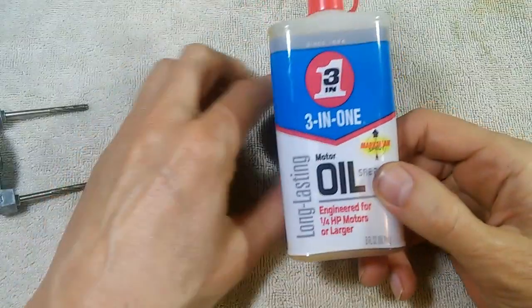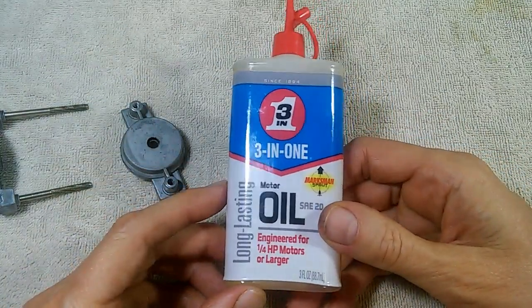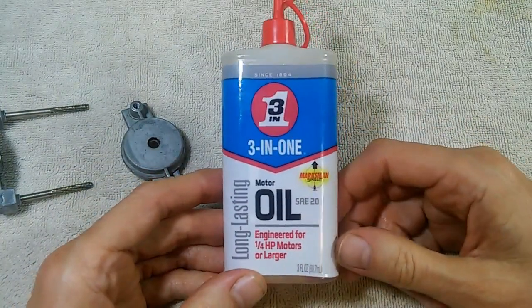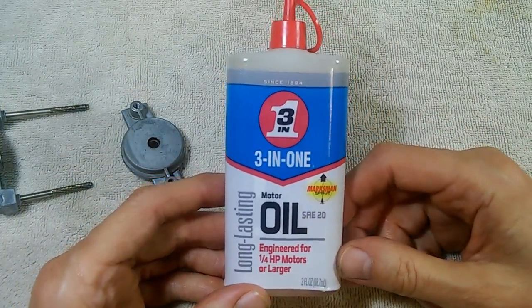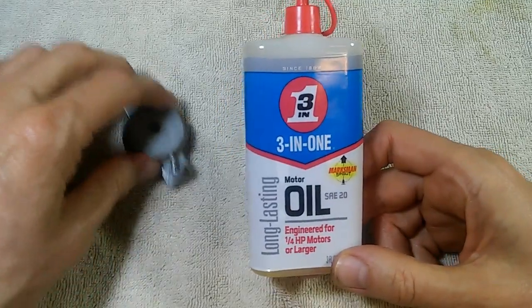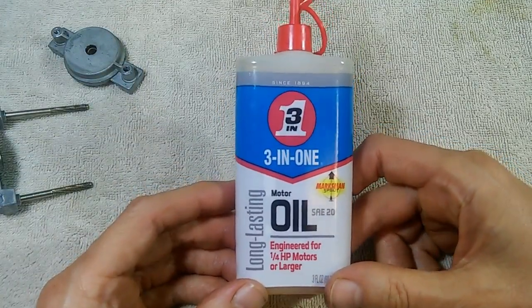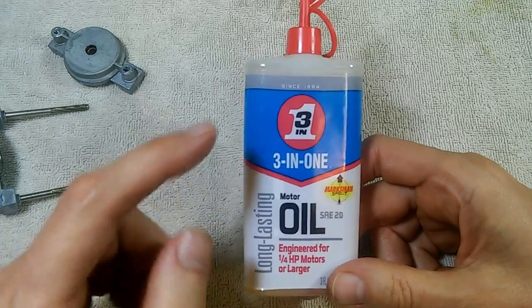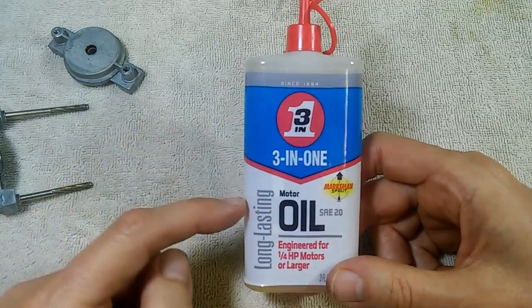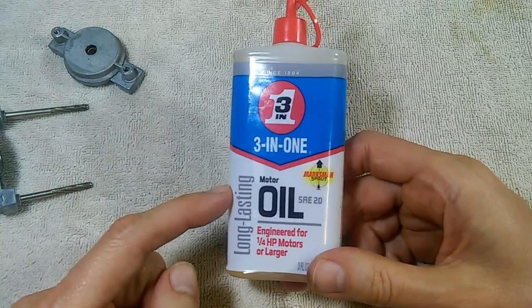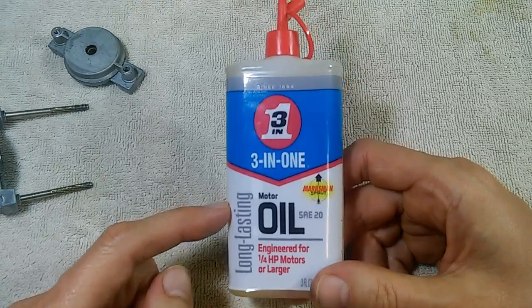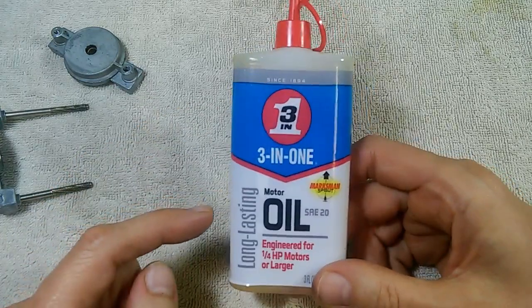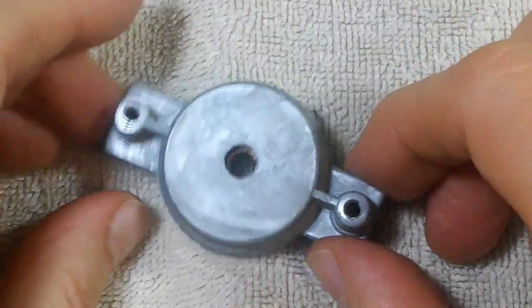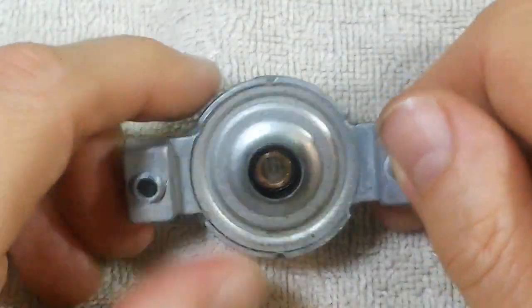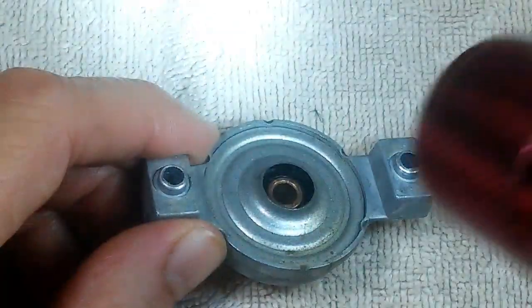I'm going to lubricate the bearings with this oil, from the 3-in-1 company. This is not the normal multi-purpose 3-in-1 oil found almost anywhere, that can is black and white. This is the blue and white can, designed for electric motors. You don't use the black and white type, use this type. Now where do we apply the oil? If we look inside this bearing here, maybe with a little bit of light...